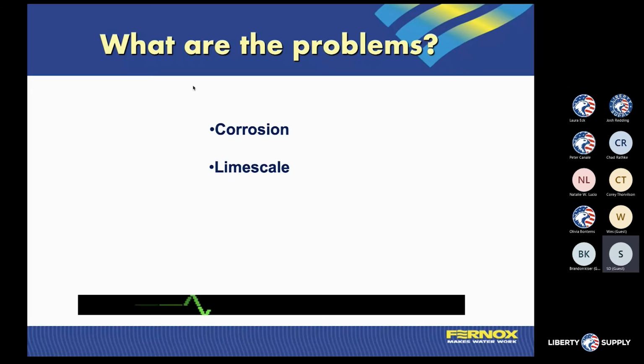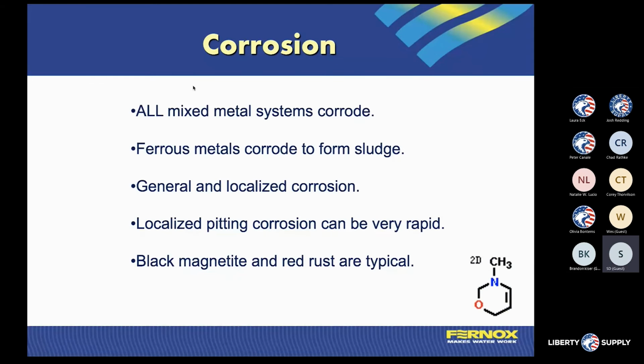There are some places where the water comes from the river, so we're not going to have so much of a limescale issue because it's coming up from the water bed instead of going down into the aquifer, but we will still have a corrosion problem from a level of pH. In a lot of cases, that still has a pH issue from that standpoint. So we're going to talk about how the system is put together.